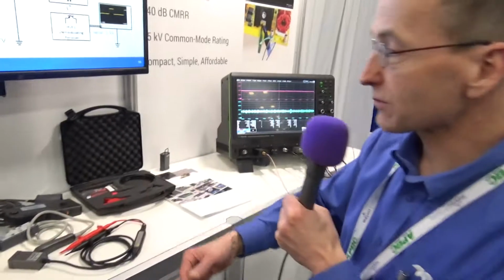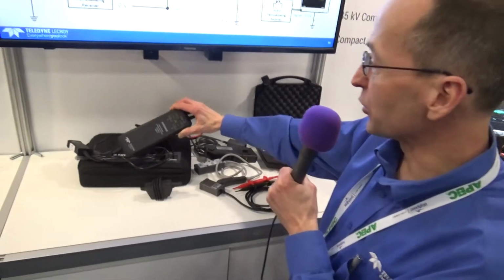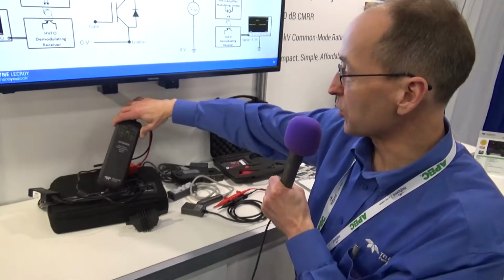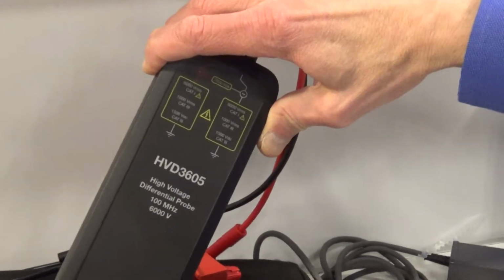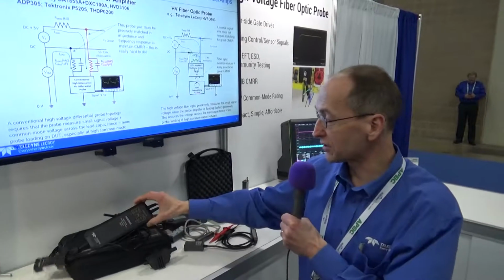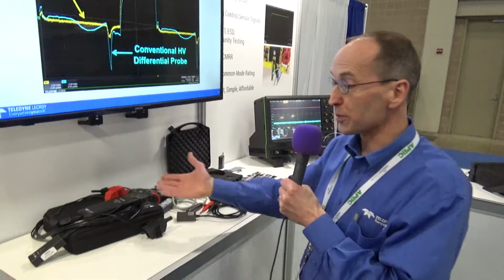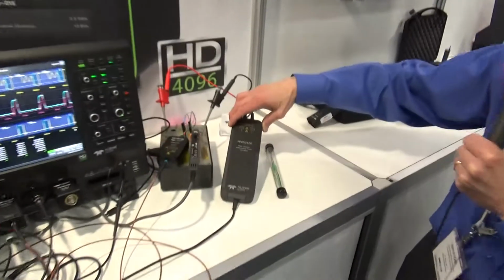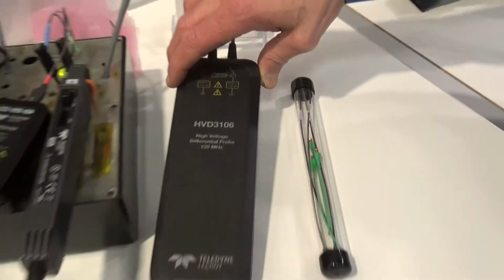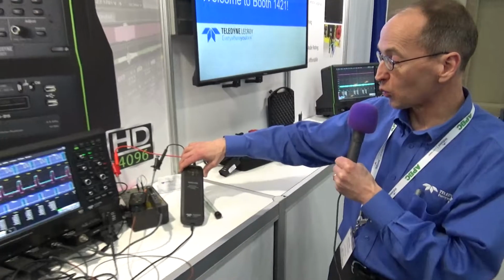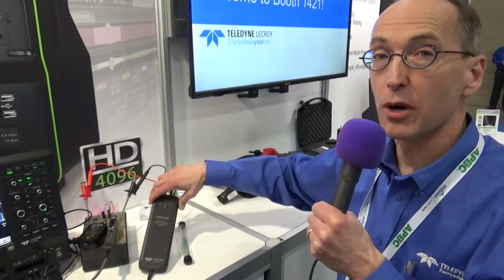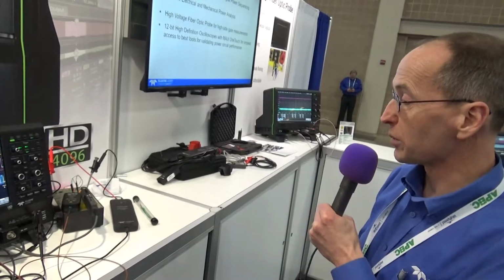If we move over here, we've got a wide variety of our probes. This is our high voltage differential probe product line. It's our HVD series. This one is a 6 kV differential probe, 6 kV common mode. It has a 7.6 kV voltage swing, and it's really the best probe. We also have a probe like this, rated 2 kV, which is great for 1500 volt DC buses for solar PV inverters or welding equipment or UPS systems. And this is the workhorse at 1 kV, which is very common for 600 volt class or 240 volt class products where you have a 1000 volt or a 500 volt DC bus. These probes, all of them, are 1% DC gain accuracy, 65 dB CMRR at 1 megahertz, and very, very high offset capability. So very unique. It's really a very unique probe in the industry.